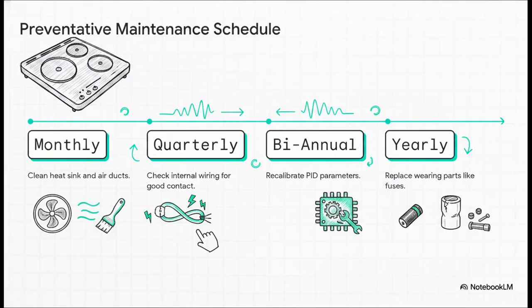To wrap up the technical advice, especially for those of you running commercial kitchens, you really want to avoid these repairs entirely. Adopting a strict preventative maintenance schedule is key. Monthly, get in there and clean the heat sinks and air ducts to prevent those annoying E5 over temp errors. Quarterly, check the internal wiring just to ensure vibrations haven't loosened any high current contacts. Biannually, for those advanced commercial units, you can actually recalibrate the PID software parameters. And yearly, be proactive. Replace wearing parts like fuses and those hard-working electrolytic filter capacitors well before they bulge and fail on a busy Friday night.